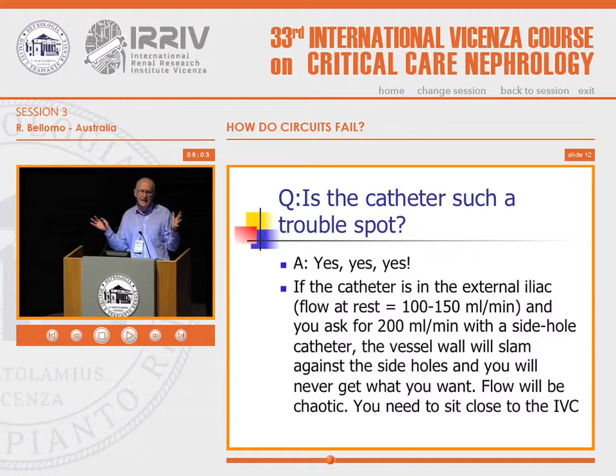And if you do Doppler estimates of external iliac blood flow, if somebody is lying in bed, it's about 150 to 120 mils per minute. So if you've got your catheter in there and you ask for 200, it ain't going to happen. And what's going to happen, particularly if you've got side holes, is you're going to suck the walls of the vein into the catheter, and the more you want, the less you get. So there is clearly a problem with the catheter in this regard.